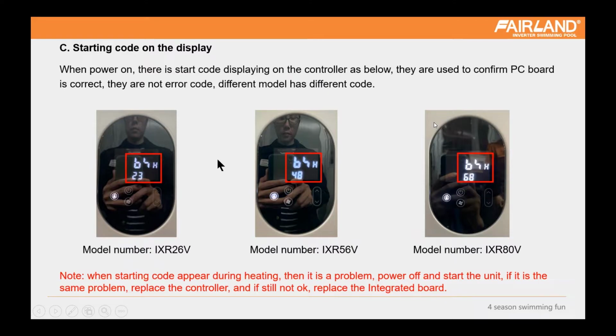Next is the starting code. When you power on the units, the units will display some code by itself. But it is not a failure code. Sometimes the customer will consider it a failure and show it to us, but it is fine. This code is just for self detection, normally for our factory's internal use. It's not a problem, but in one special situation, it is. If our unit keeps running and heating, but suddenly this code displays and stops the unit, then it's a problem. Normally we have to reset the unit to check if it can be recovered. If not, we have to replace the board.